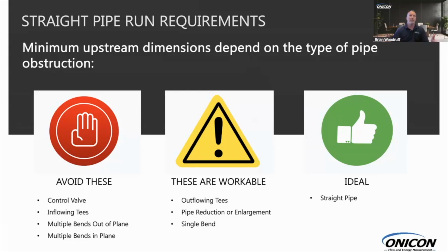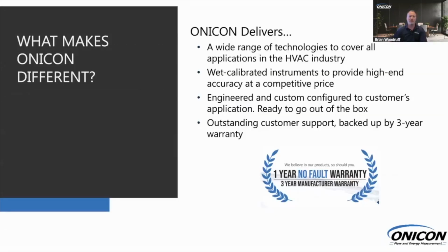An example is we were on a building one time and they had roughly, say it's a 10-inch pipe, they had 100 feet of straight run. Well, the mechanical contractor just went 10 pipe diameters, installed the meter, and then they had 90 pipe diameters downstream of the flow meter. So in that case, we definitely always recommend, like say, the 80% upstream, 20% downstream rule. You want to give yourself the longest amount of straight run possible from that obstruction to your flow meter to get the most accurate measurement. Back to Mike to wrap up for us.